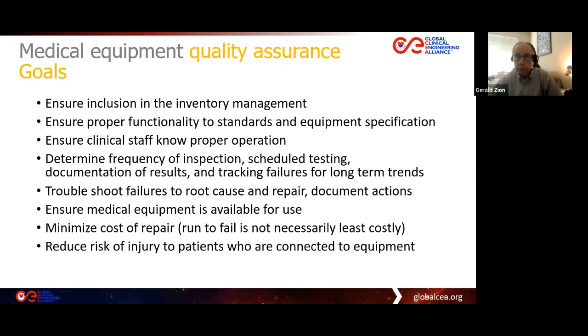We want to troubleshoot failures to root cause and correct the problem through repair or adjustment or whatever. And then we want to make sure we document those actions. And by the way, if we bring a manufacturer's field service engineer or an independent service provider in to do those repairs, then we need their test report in order for us to have the proper information to document what the root cause of the problem was, and that the repair actually was effected. And then we want to repeat the testing after the repair to make sure that the medical equipment is back to specification.